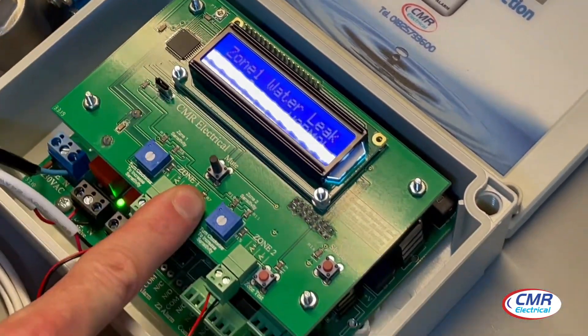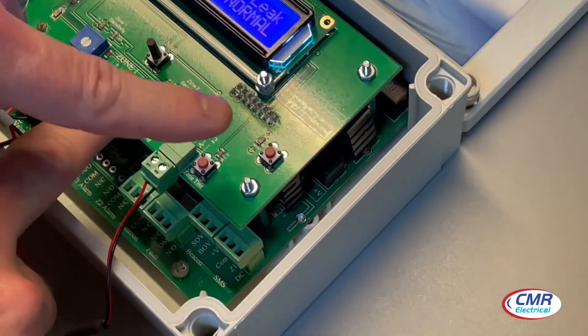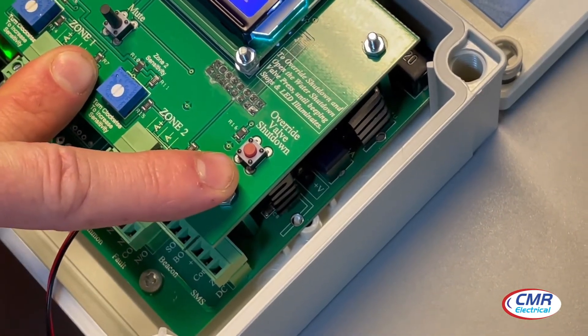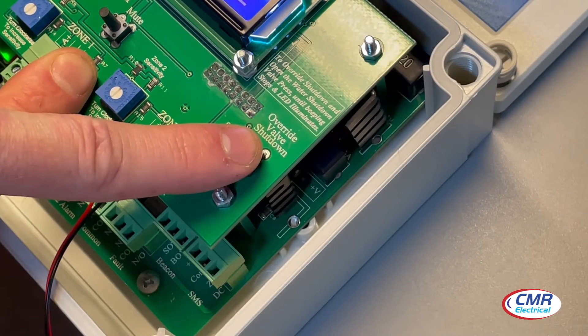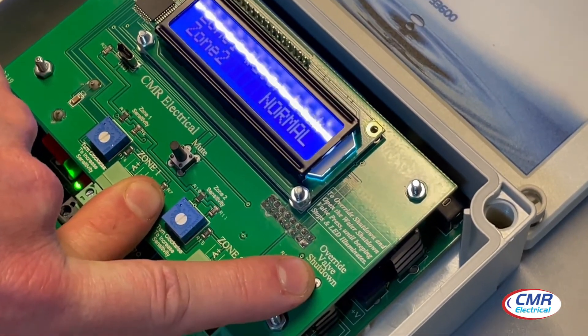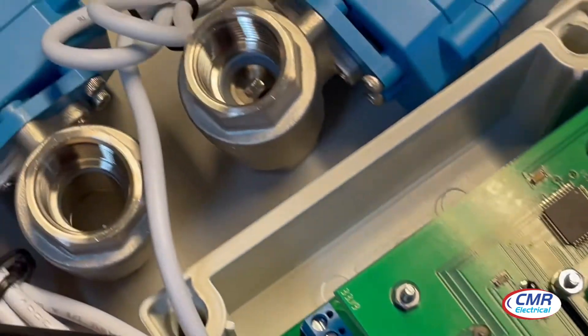Over here, if you need the water supply to come back on, we have an override facility. A little red button there says 'override valve shutdown.' If you hold that down for five to six seconds, it will open the valve back up, allowing the water supply back on.